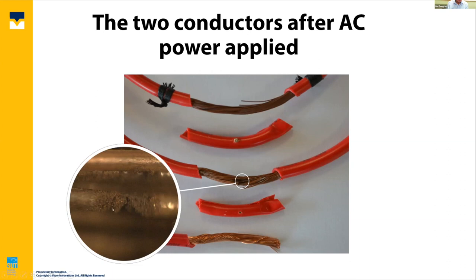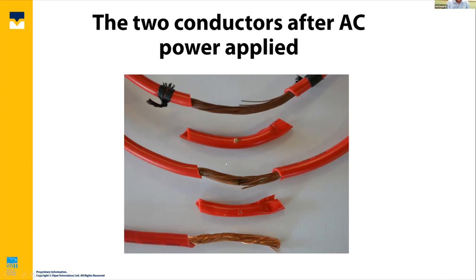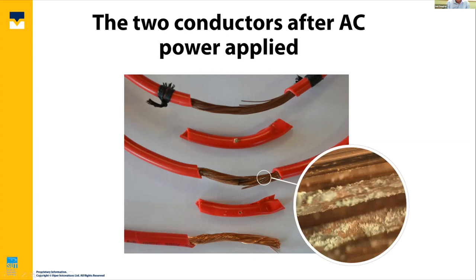Here's one wire that is being eroded through that electrochemical reaction, and the wire is about to break. So again, this electrochemical reaction is resulting from simply applying power, 220 volts, to these two wires. There's nothing on the end of the wires. There's no load or anything. All we're doing is applying a voltage between the two wires, and they both have an insulation resistance failure to ground. And again, we see some of that original salt, sodium chloride, on the wires, which again is just demonstrating that seawater is penetrating into the wires.